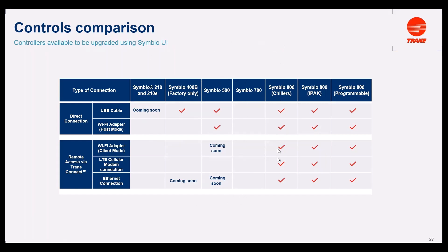In the case of the 700, there is no UI available for the Symbio 700. To conclude this table, for the 800 — in the versions for Chillers, IntelliPack, and the programmable — you can use all the possible ways to upgrade the firmware. For direct connection, you can use a USB cable or the Wi-Fi adapter in host mode. For remote access using Trane Connect, you can upgrade the firmware using Wi-Fi adapter in client mode, LTE cellular modem connection, and Ethernet connection.